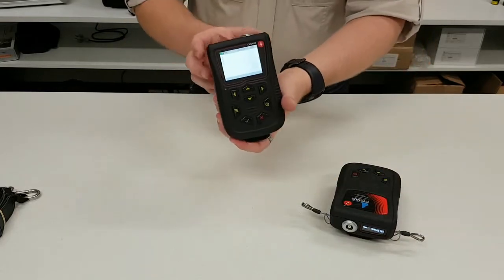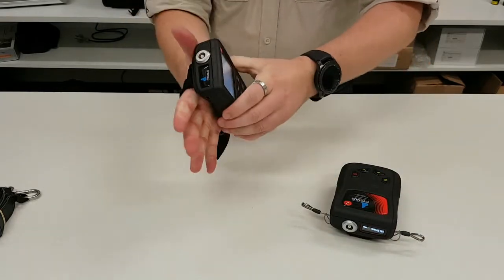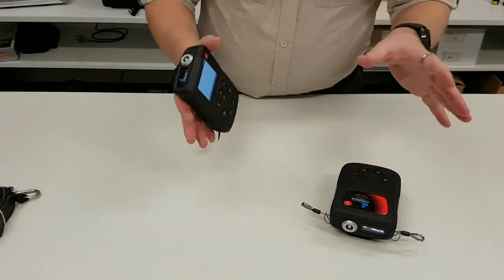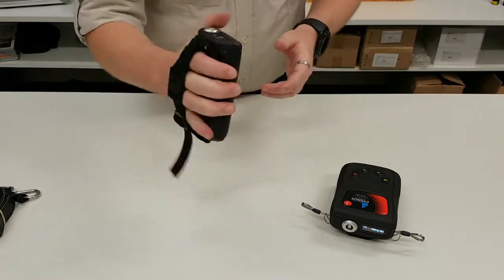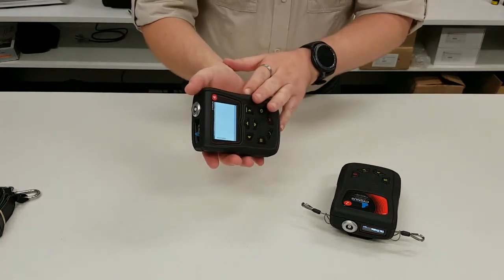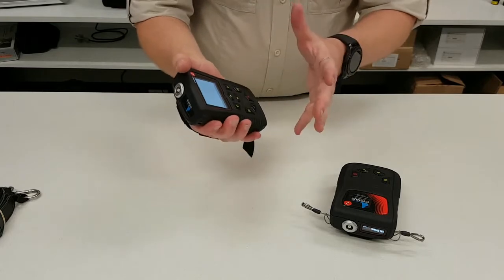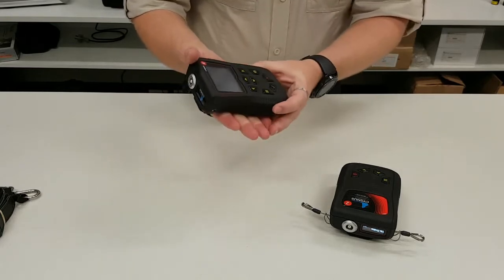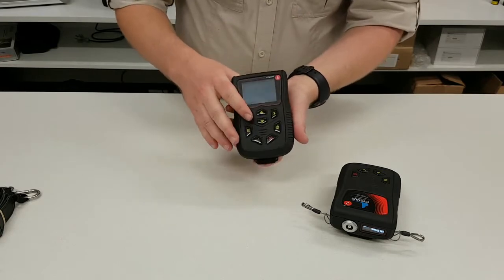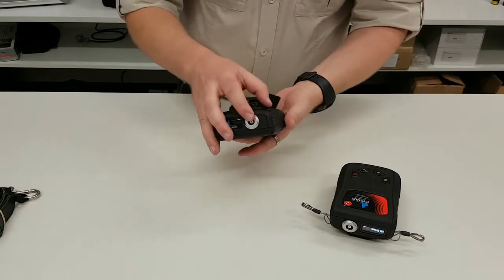The Cygnus IV on the other hand is a general purpose gauge. It has a large OLED display on the front, which is very simple to read. That's pretty much where the differences end — they both have the same nice solid feel, both twin shot injection moulded bodies, so they're both IP67 rated and going to take a fair bit of punishment. The buttons on the front are all rated to 100,000 depressions, and on the top you've just got a standard LEMO 1 connection.